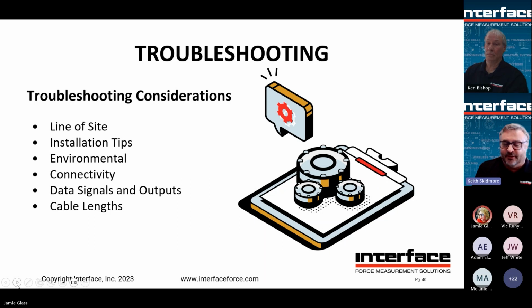Again, signals and outputs, maybe some incompatibilities. If it's 4 to 20 and it's scaled so that you get 4 to 20 in tension, but the load cell is only being used in compression, or vice versa, you can have issues. So it's important, again, to look at the signals and whether they are compatible with the devices.